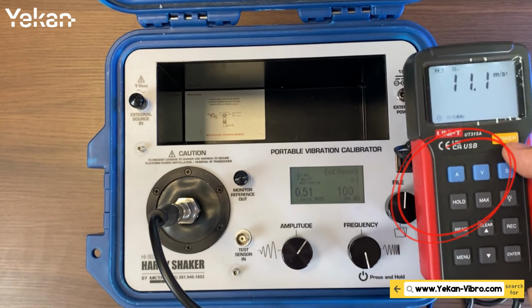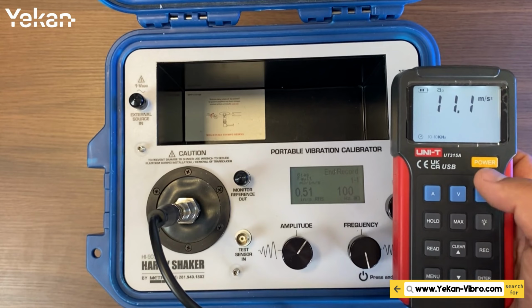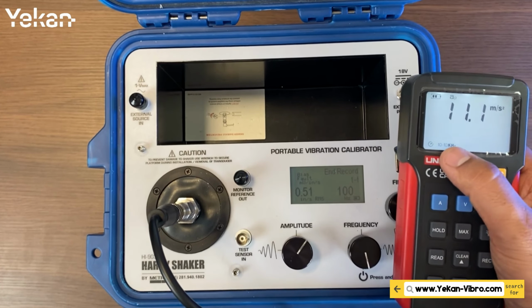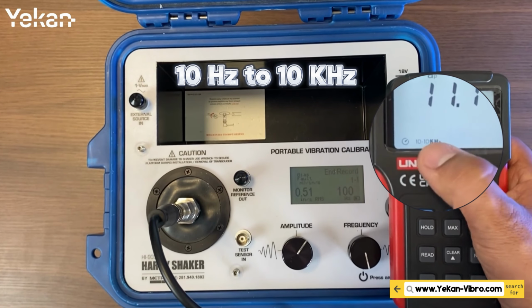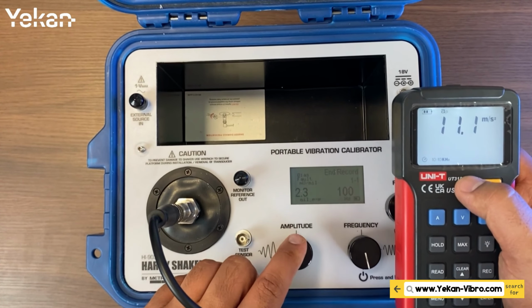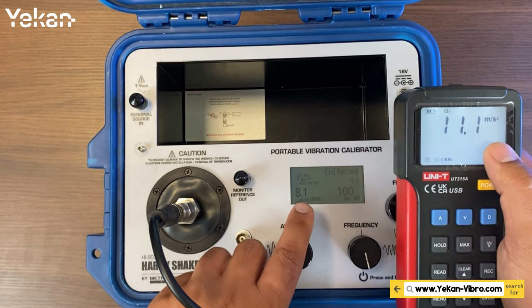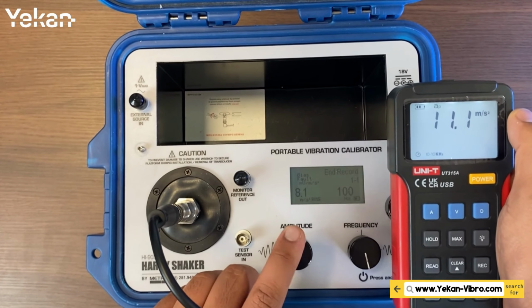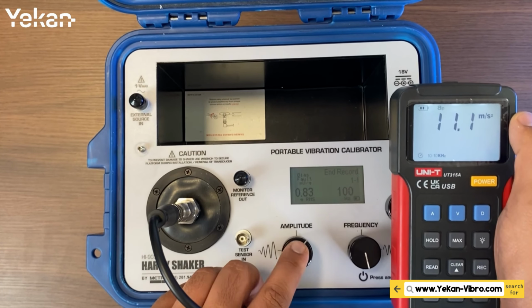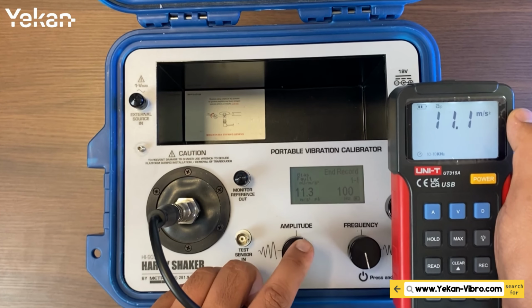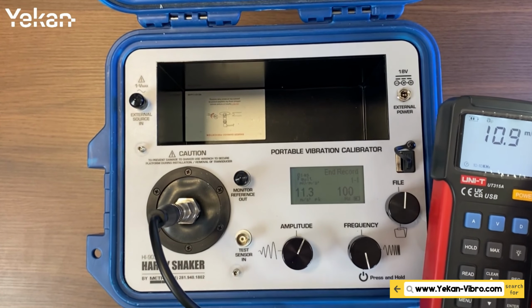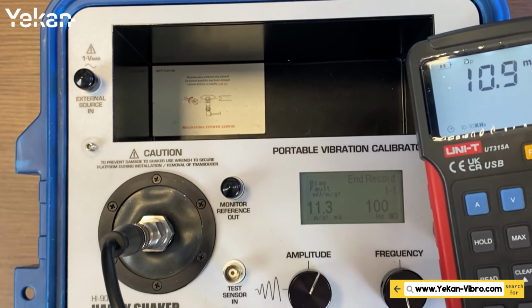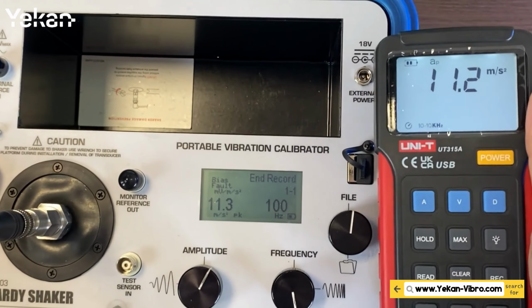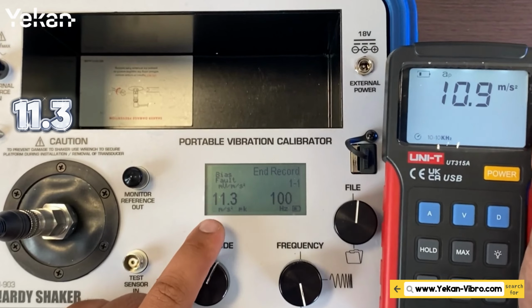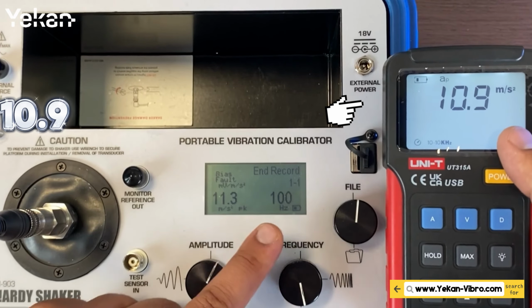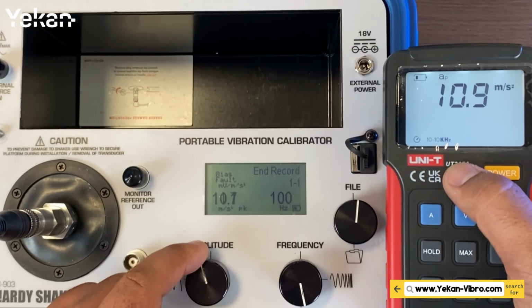Here we can, with its buttons, choose acceleration, velocity, displacement. We select acceleration. The range it wants to show is between 10 Hz to 10 kHz. Less or more than those it wants to filter. Of course, this range is adjustable. The calibration form we also put on meter per second squared RMS, but here it is peak, meter per second squared peak. Here in the picture reference, it produces 11.3 meter per second squared peak at frequency 100 Hz. Here we get 10.9. Well, here we can do two tests: frequency test, sensitivity test.